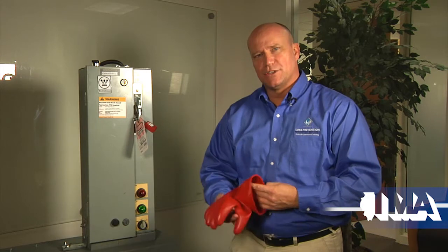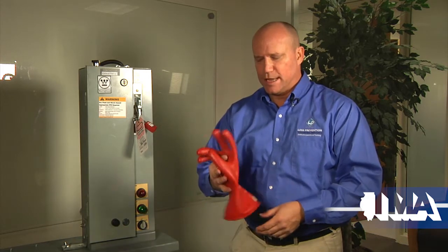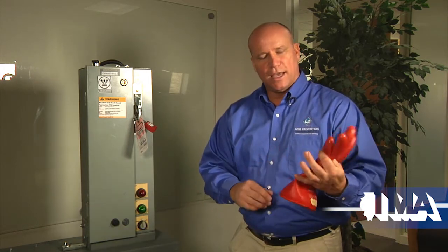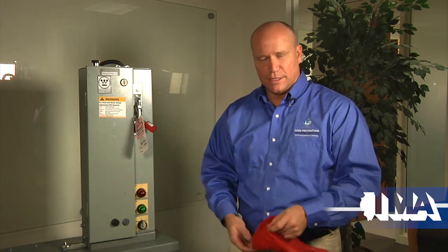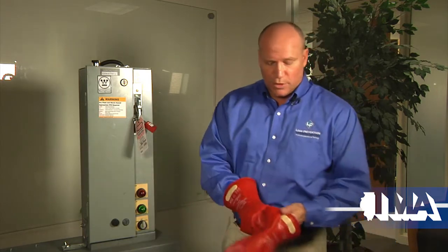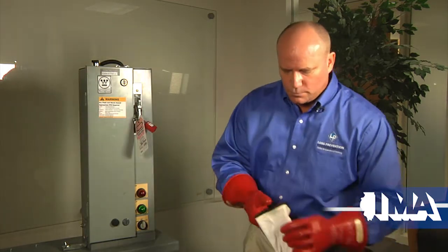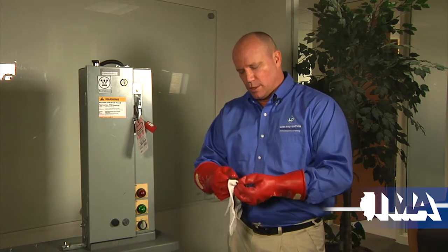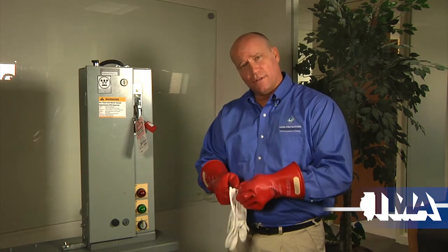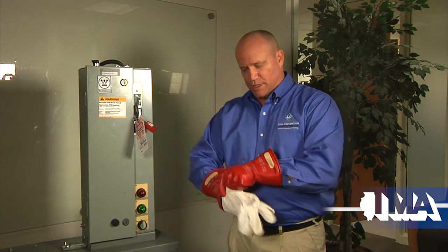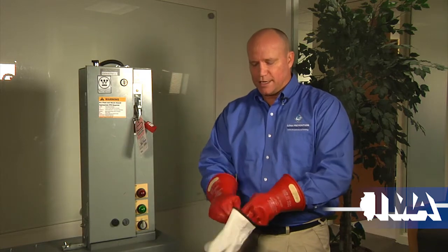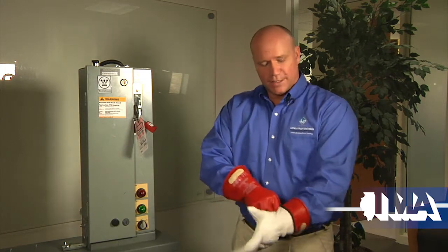Okay, every 6 months they should be sent out to a testing laboratory to go ahead and do a high voltage test on it to verify that the glove isn't damaged, an integrity issue that you can't find during a visual inspection. So I'd go ahead and put those gloves on. Always you'll be putting a pair of leather gauntlets on. And the reason for that is you want to protect your hands from an arc blast.